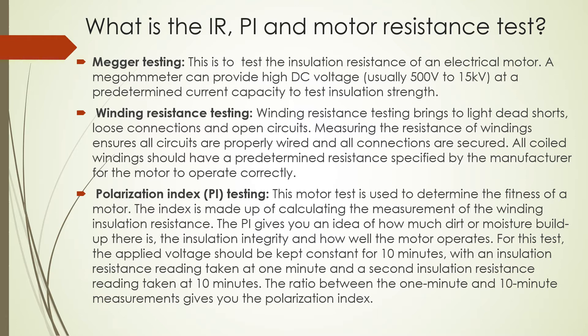Polarization Index or PI testing is used to determine the fitness of a motor. The index is calculated by measuring the winding insulation resistance. The PI gives you an idea of how much dirt or moisture has built up, the insulation integrity, and how well the motor operates. For this test, the applied voltage is kept constant for 10 minutes, with an insulation resistance reading taken at one minute and another at 10 minutes. The ratio of the one-minute to ten-minute measurement gives the polarization index.